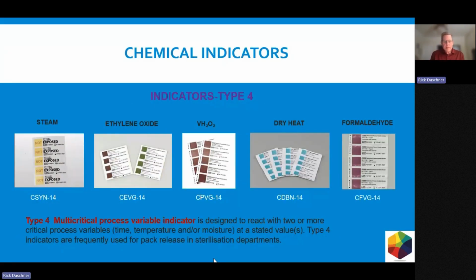So type 4s. We've gone from type 1s, and type 1s, again, was it processed? Was it not processed? Type 4 adds a couple more parameters to it, and it's designed to react to 2 or more critical processes: time, and then temperature and moisture as stated values. So our stated values on the product, you can see on our data sheet. And this will give you a little bit more of a response to say, yes, it was processed, and yes, it did meet the temperature or moisture parameter.